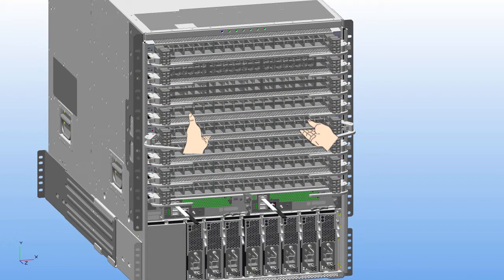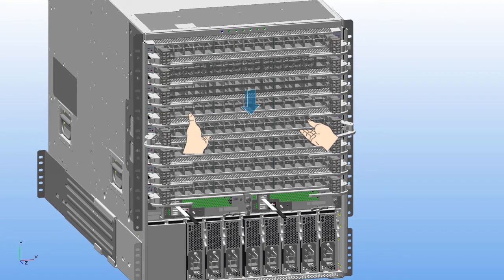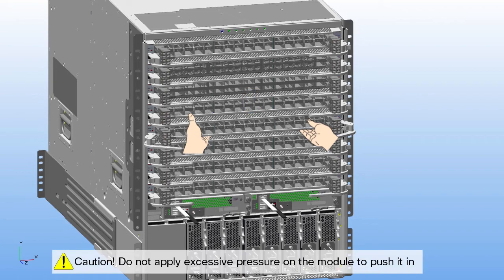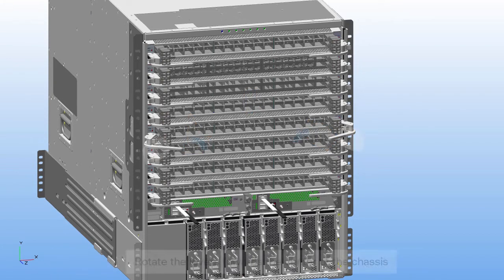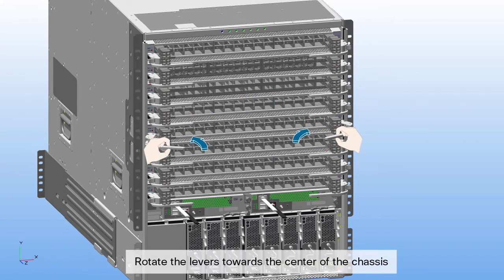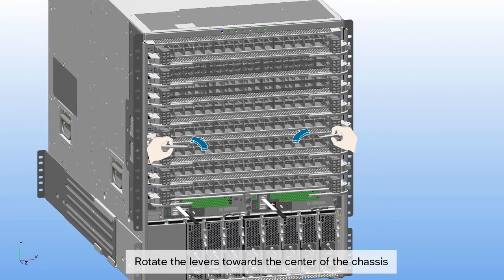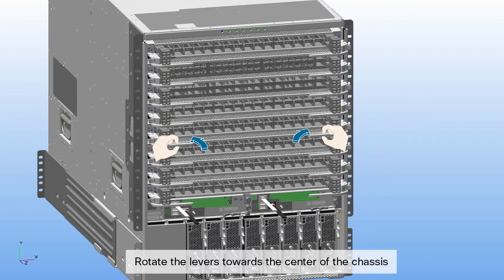When the module is completely inserted, it protrudes out by 0.25 inches in front of the chassis. Warning: do not apply excessive pressure. Rotate the ends of the two levers toward the center of the chassis.